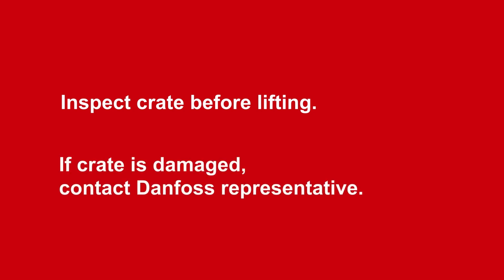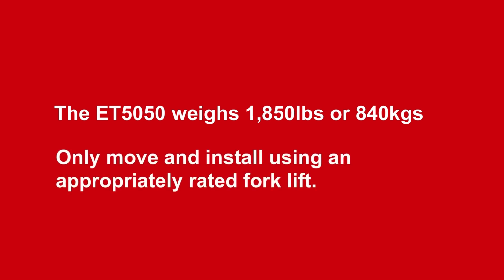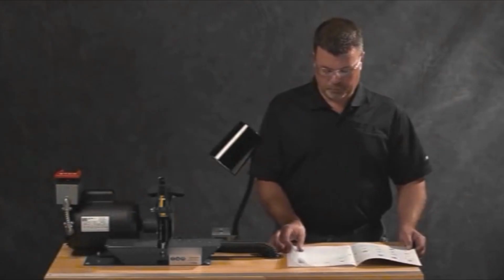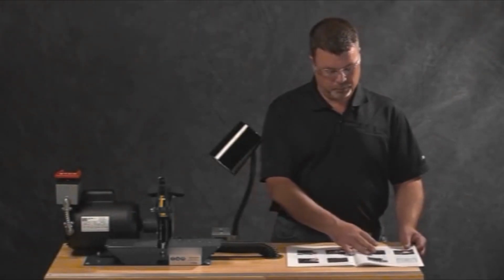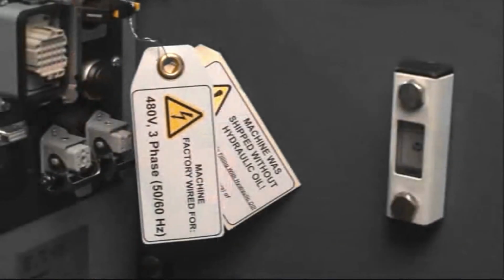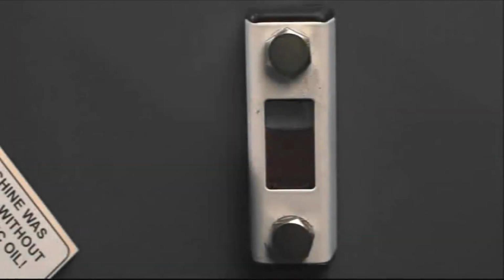After receiving the ET5050 shipping crate, inspect the crate for any external signs of damage prior to lifting. If damage is evident, contact your Danfoss representative immediately. The ET5050 weighs 1,850 pounds or 840 kilograms and should be moved and installed using an appropriately rated forklift only. Refer to the operator's manual for machine installation instructions, height adjustment, electrical connection required, and to fill the hydraulic reservoir.